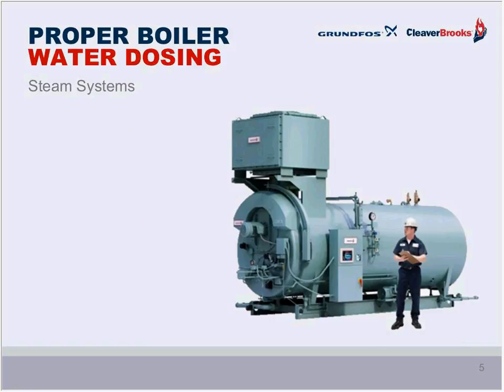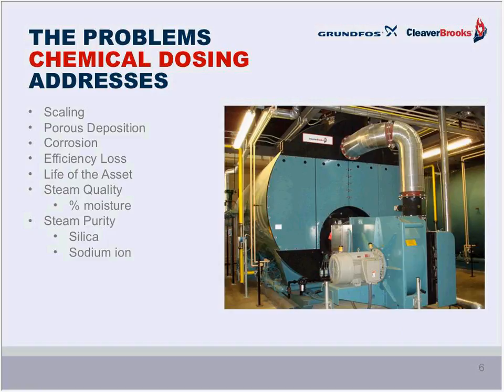Starting with the boiler, the place of highest heat release, there are a number of potential problems that we need to contend with in order to protect this very valuable piece of equipment. Deposition of material on the heat transfer surfaces of the boiler causes significant energy loss and possible vessel failure, which affects the life of the boiler, along with costly downtime, as I mentioned. And there's the question of how steam leaving the boiler can affect the process or the piping system due to impurities in the steam or excessive moisture, causing serious water hammer and damage to the connected piping.